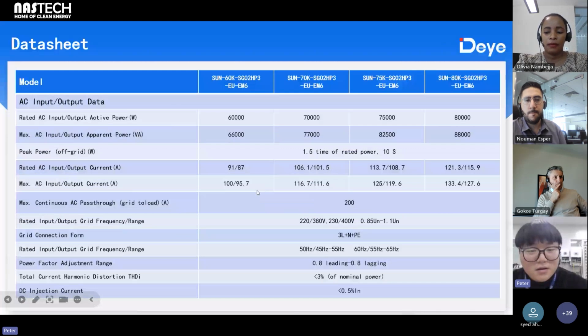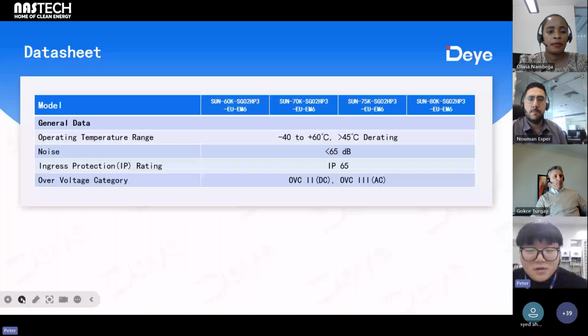And the peak power is 1.5 times the rated power. Which means as long as your inductive load start power is within 1.5 times the rated power, then the inverter can start the inductive load, even in off-grid scenarios. And the other parameters are basically similar to the 50K.